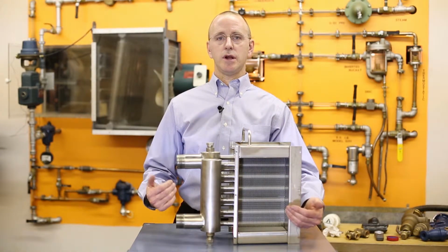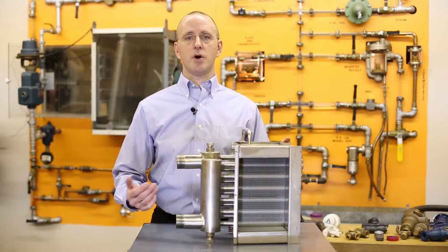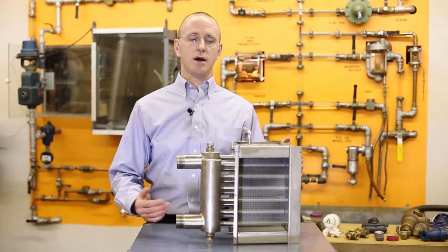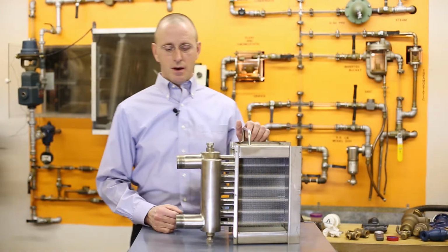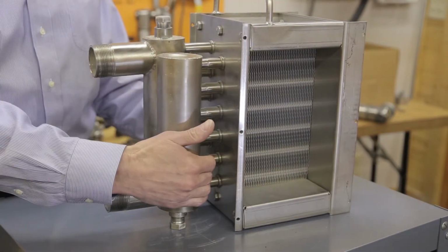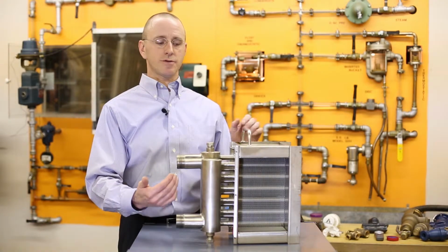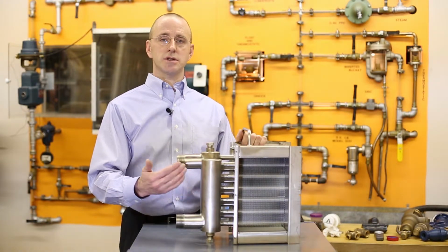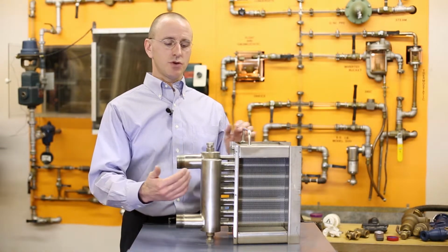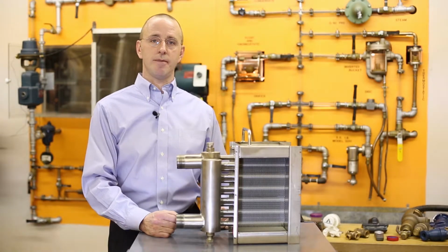If we're doing cooling, we need to know whether we'll be doing any condensing. So we'll need to know the wet bulb and dry bulb, or humidity ratio, or the relative humidity of the air blowing across the coil. On the fluid side, we can do everything from 3/8 inch tubes to 1/2 inch tubes to 5/8 inch tubes, and we offer many different circuitings from 1/6, 1/4, all the way to quad circuiting to match the fluid pressure drop and fluid velocities that you'll need to do the job.